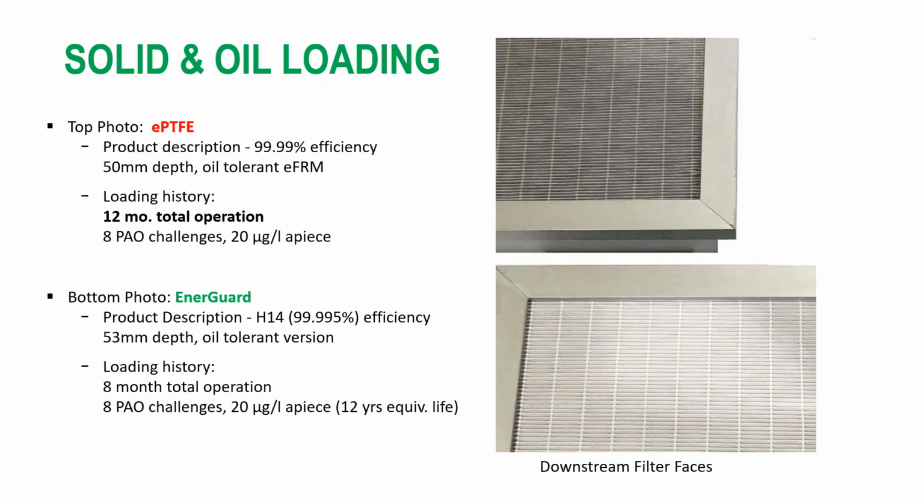At the same time, they did another test with the EnerGuard media, and in that case, this is again the oil-tolerant version, the basic microelectronics version, and then there's also an oil-tolerant version for life science and bio. In that case, it was running at 8 months total operation with 8 PAO challenges at the same concentration, but again did not see any type of breakdown in the material or fast loading the way that was seen with ePTFE.